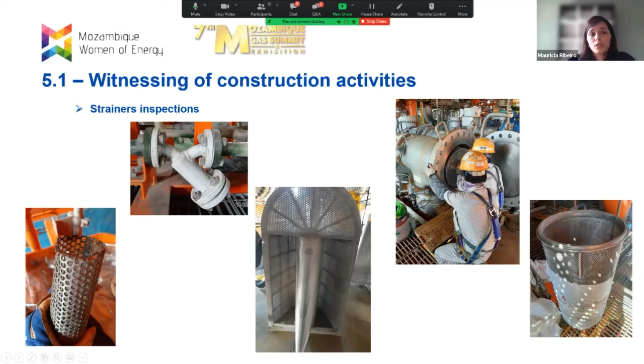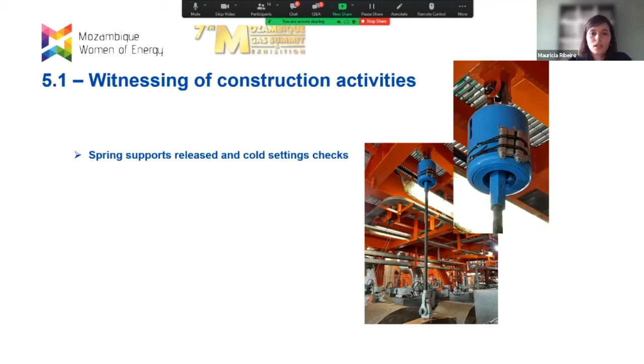Something we also do is checking of the spring supports. Spring supports are, as the name says, not fixed supports, so they can hang a little depending on the fluid inside. We check that the support has been released, meaning those pins have been removed. We keep the pins in case we need to put them back later for maintenance or towing in this case. We also check, though it's hard to see in the picture, there's an arrow showing the cold setting and the hot setting to be sure the spring support has been correctly released.